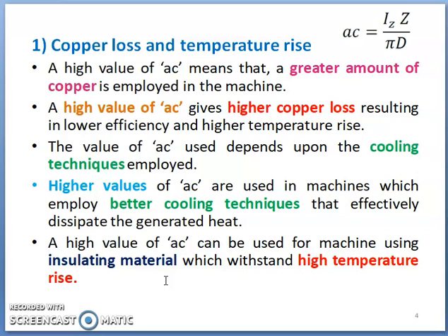results in temperature rise. In order to ensure reliable and satisfactory operation of electrical machines, the heating of every part must be controlled within specified limits. Whatever temperature rise there is will affect the insulating material put to isolate the windings from the iron part.